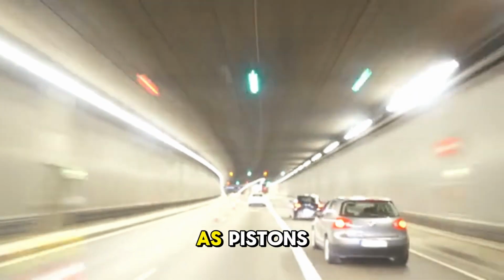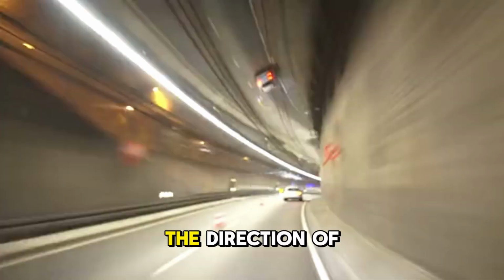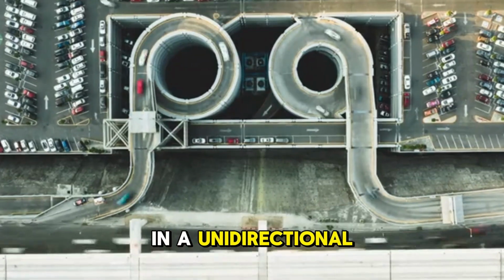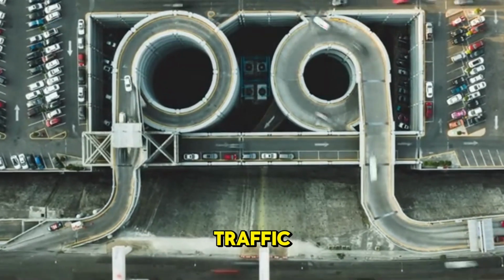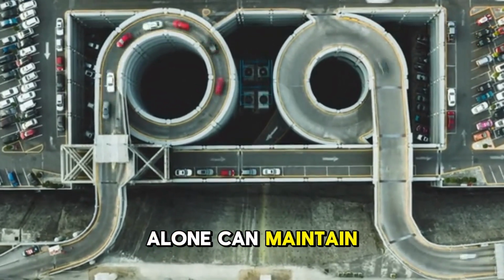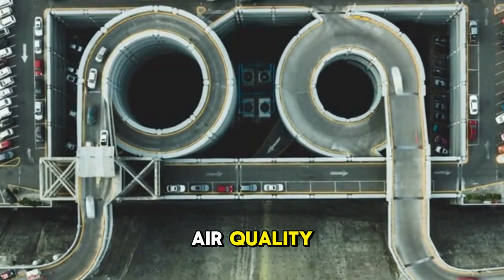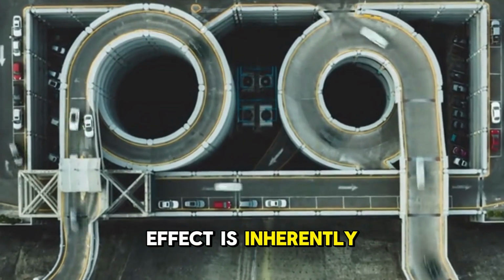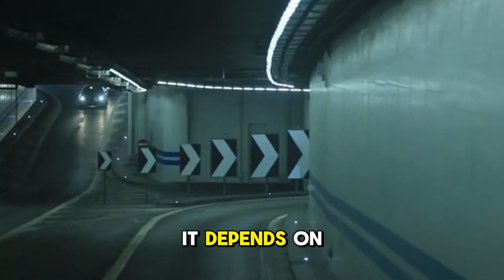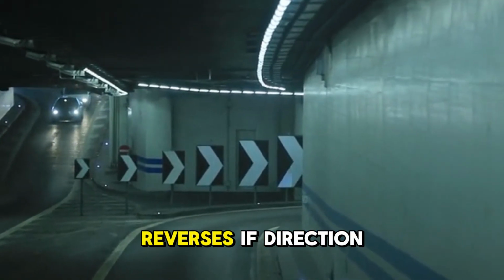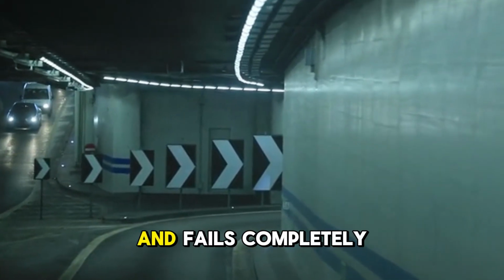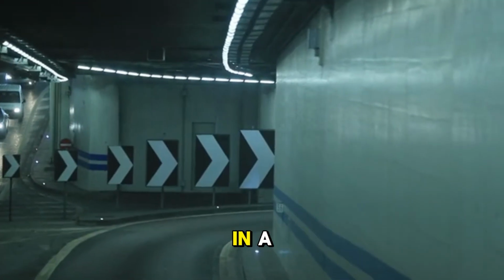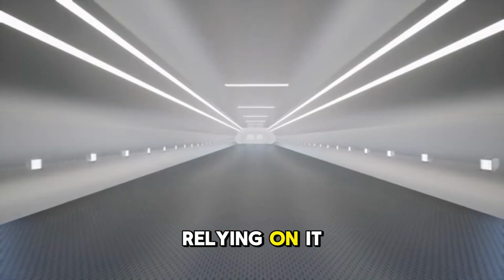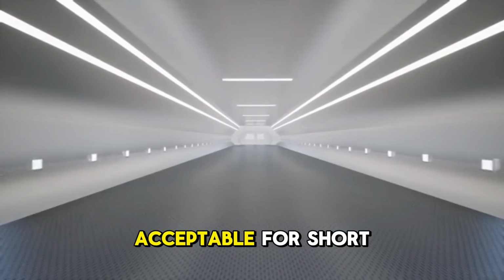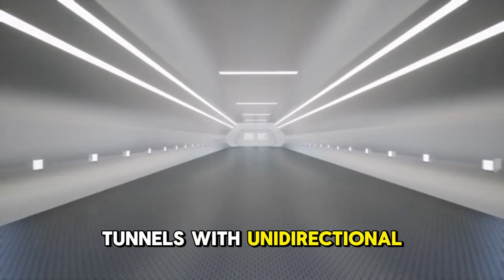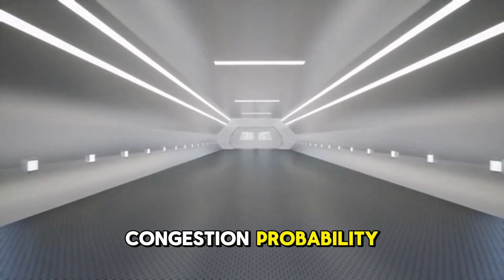Moving vehicles act as pistons, dragging air in the direction of travel. In a unidirectional tunnel with sufficient traffic, this piston effect alone can maintain air quality. But the piston effect is inherently unreliable. It depends on speed and density, reverses if direction changes, and fails completely when traffic stops in a congestion event. Relying on it as the primary strategy is only acceptable for short tunnels with unidirectional traffic and low congestion probability.